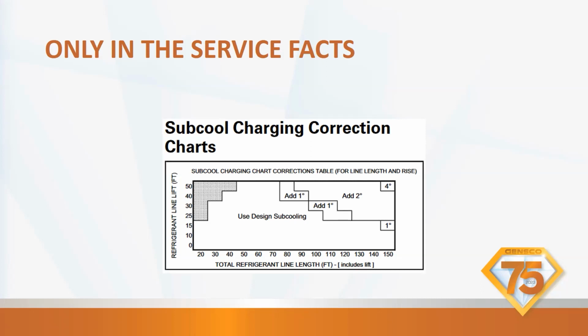Then if you have a 20-foot line set with a 20-foot rise, you see the gray over there? That means you can't really do it because it's a 20-foot line set and a 25-foot. So the bottom is your total and the left side would be your lift. So once you get up to like 80 feet, you're going to add subcooling for lift. Okay. 80 to 150 feet, you're going to be adding subcooling for lift. So just remember that's in there, and it's only listed in the service facts. This is not in the install guide, it's in the service facts.